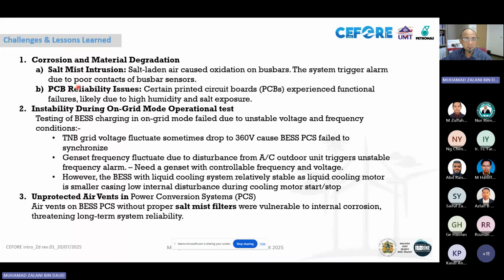For example, moisture intrusion causes our bus bar to oxidize, triggering alarms. This bus bar refers to one of the battery energy storage PCS bus bars, so it triggers an alarm because of the oxidation of the bus bar. We also found PCB board reliability issues, where some PCBs had problems due to exposure to high humidity and salt.